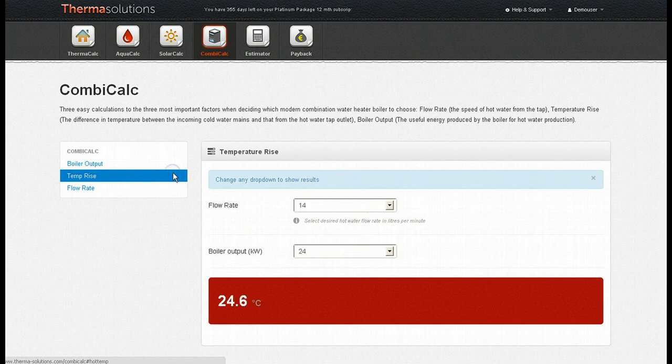To know what temperature should be coming out of the tap is a useful one, especially if the homeowner has complained about having lukewarm baths following a new installation. You need to know if the boiler is underperforming or behaving as it should. Poor temperature delivery could also be something to do with the installation.